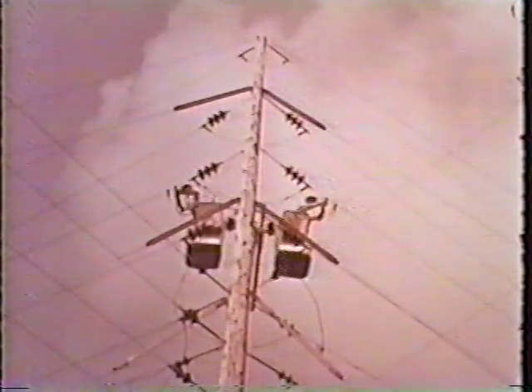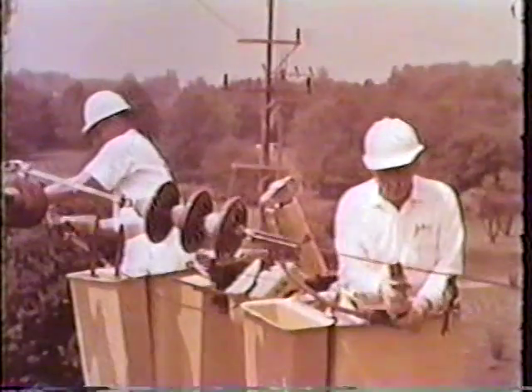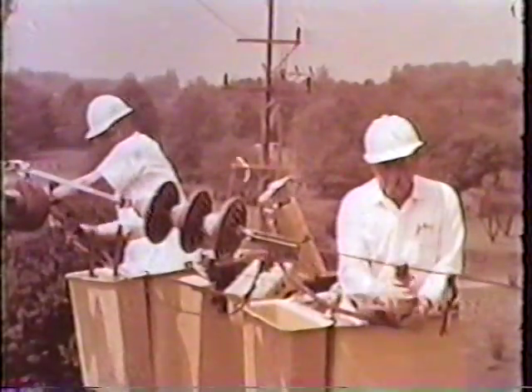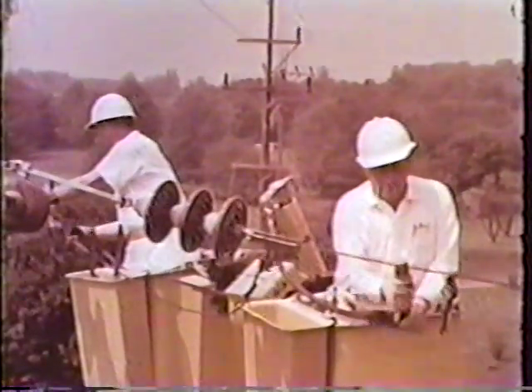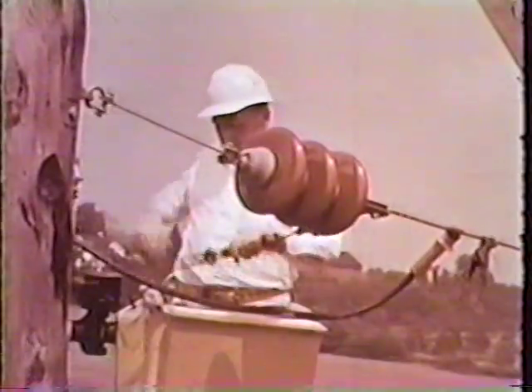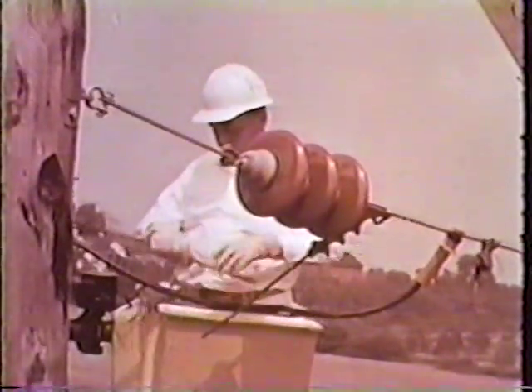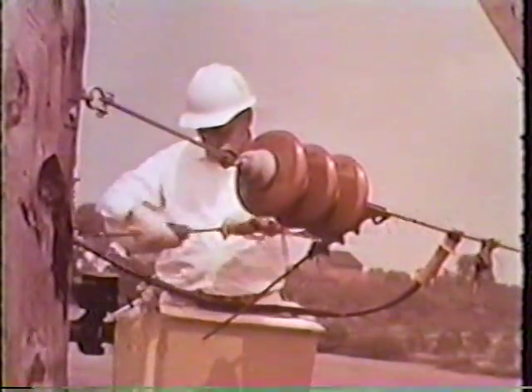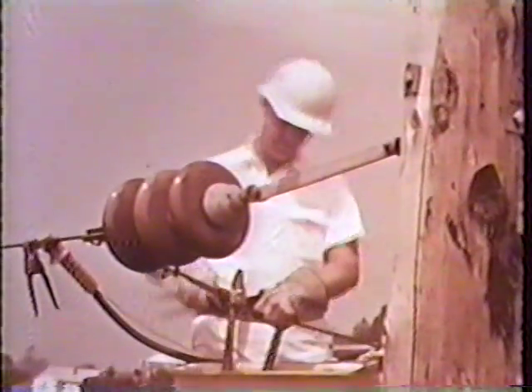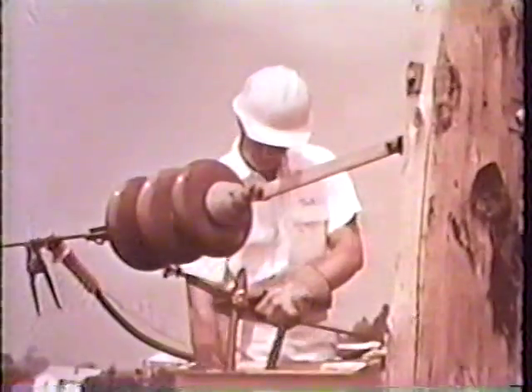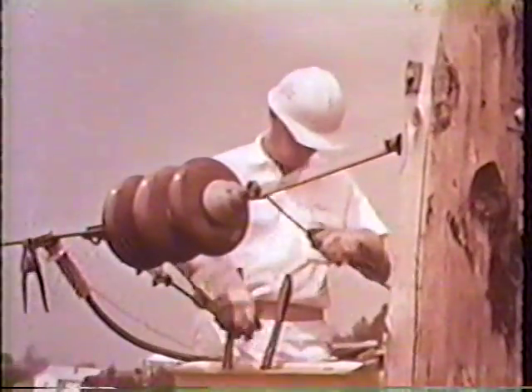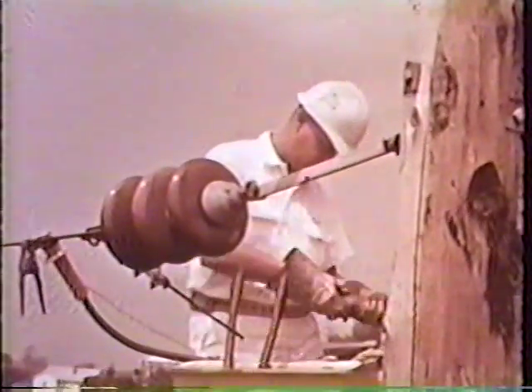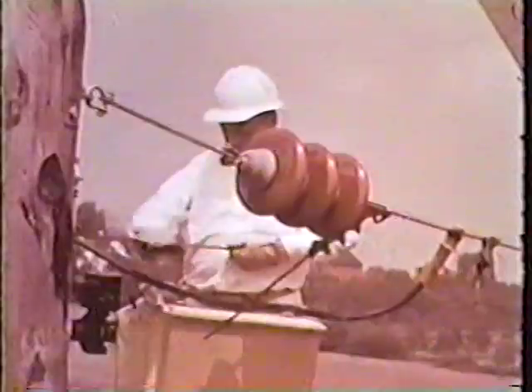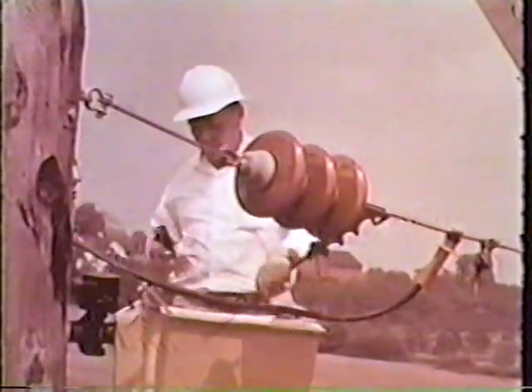Another typical bare-hand job is illustrated by the work on this 33 kV corner pole. The line current will be carried by a temporary jumper as the crew replaces high-resistance bolted connectors with compression fittings. Their buckets are equipped with manually operated swiveling devices, which permit each bucket to be rotated horizontally up to 90 degrees or more in relation to the arm, allowing each man to place himself in the most convenient work position. Buckets remain level automatically in any elbow position.